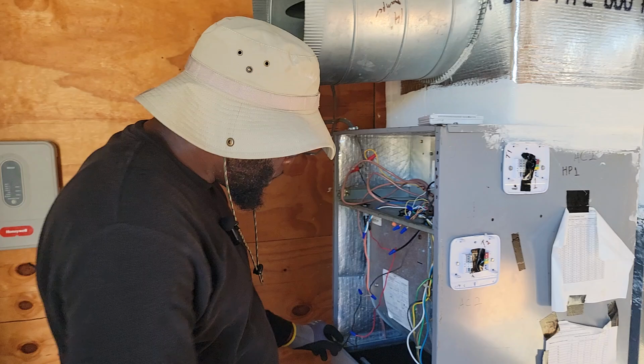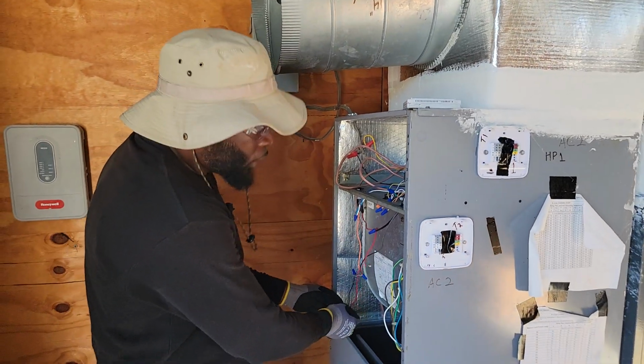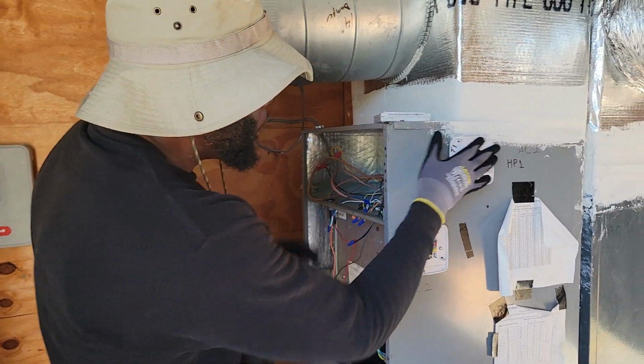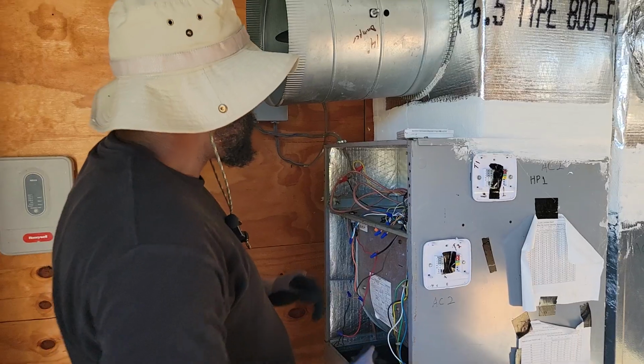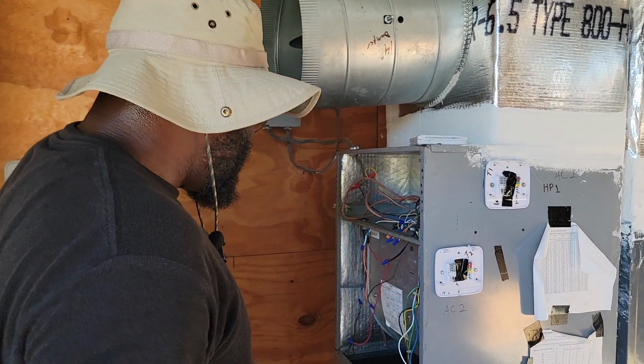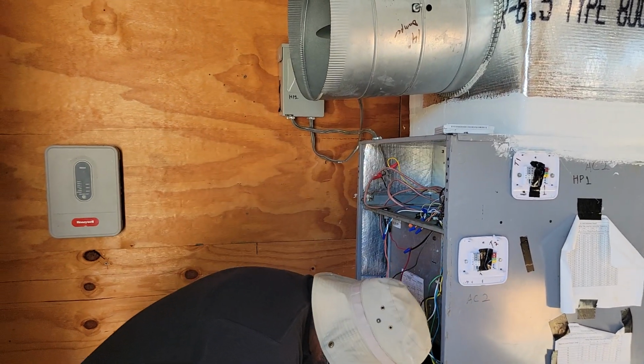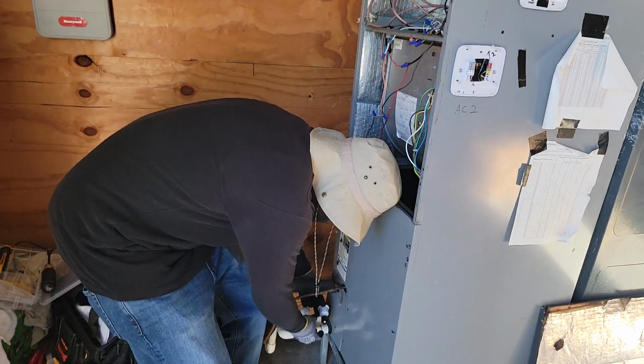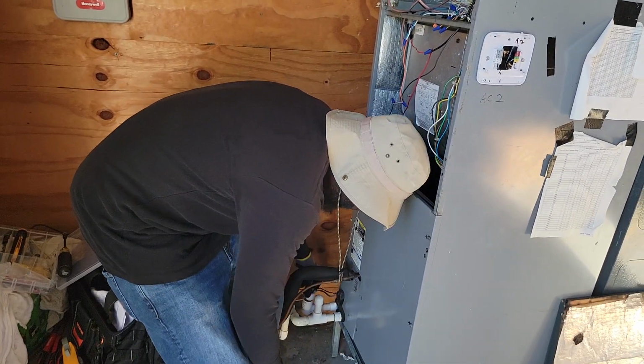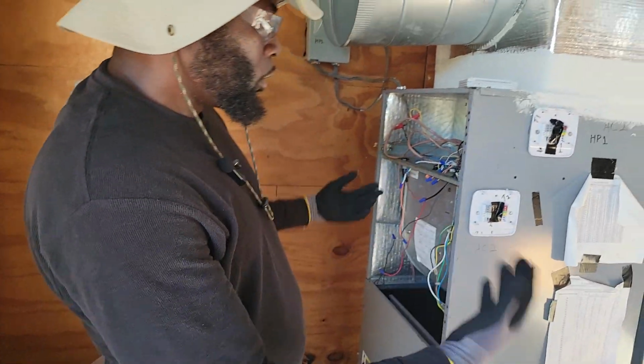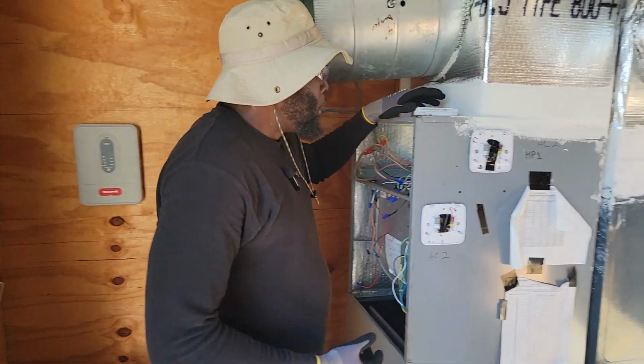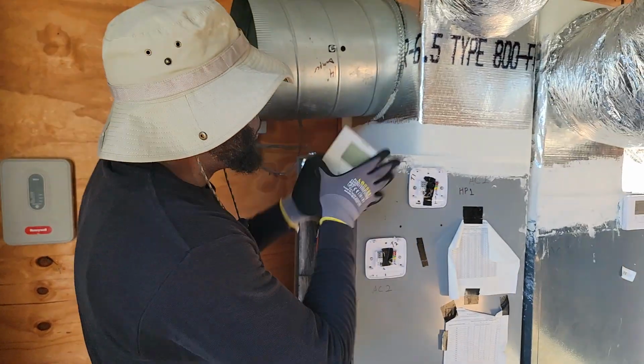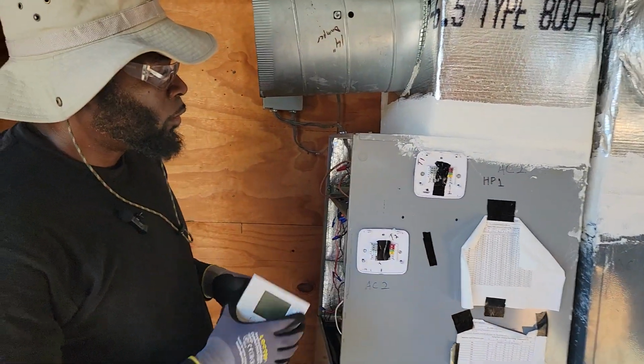So that power breaks the 24 volts that goes here, and it tells the system to shut off. And once you clear that drain line, this float switch will go back down, and the system will turn back on. It lets the system know, hey, I'm okay. Now, we're going to explain the thermostat process a little bit.